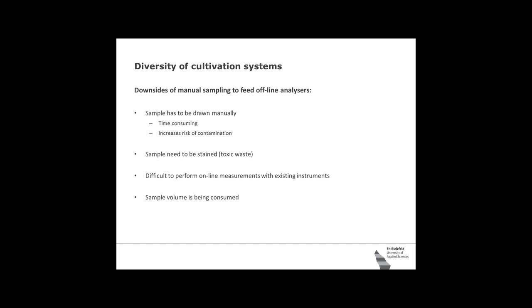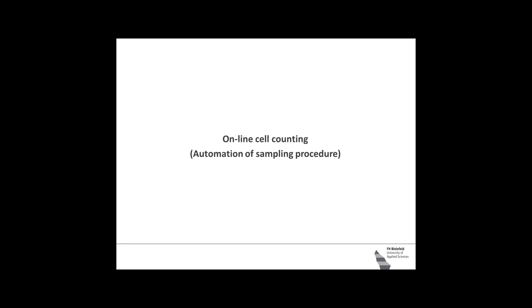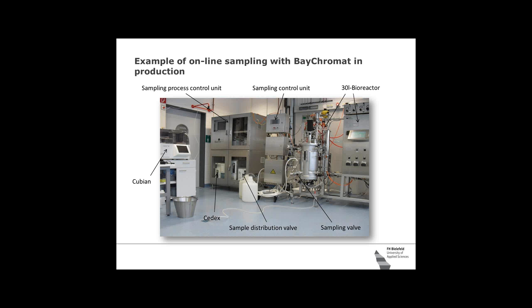The sample needs to be stained. It's difficult to perform online measurements because sometimes one measurement, one data point per day, as it is usually done with manual sampling, is not enough because you want to know more about your process. Sample volume is being consumed. Also, this is or may become an important factor while trying to automate offline counters. And that's what I named here online cell counting. It's the automation of the sampling procedure and hooking up a device that is able to count cells.